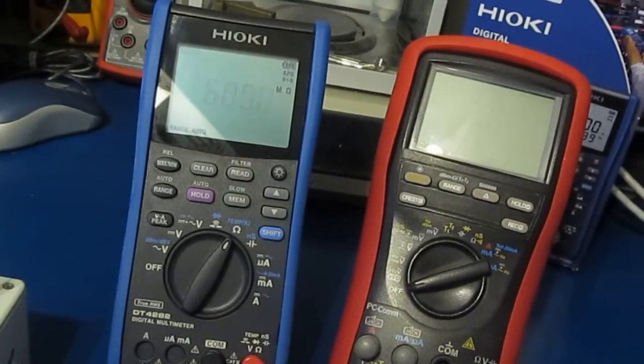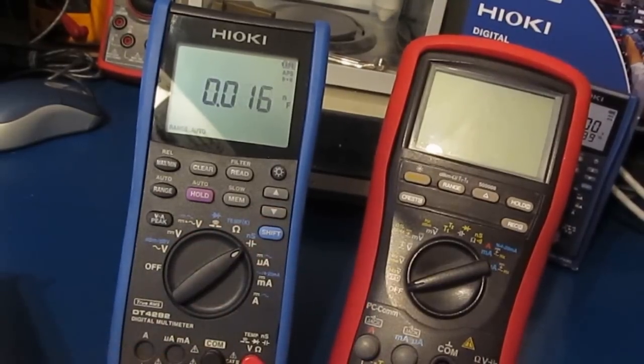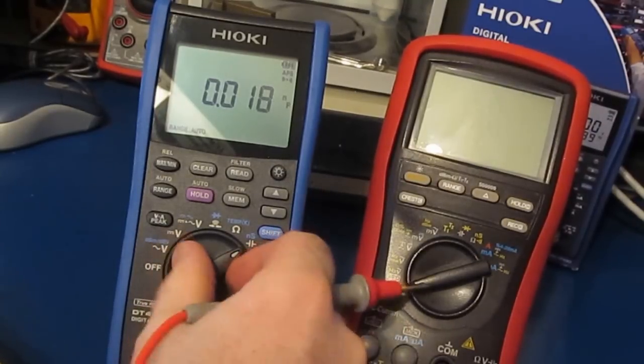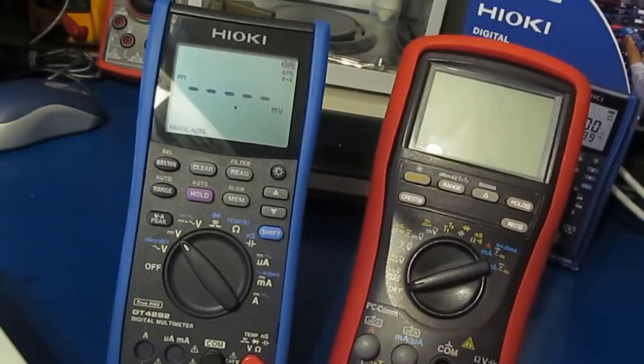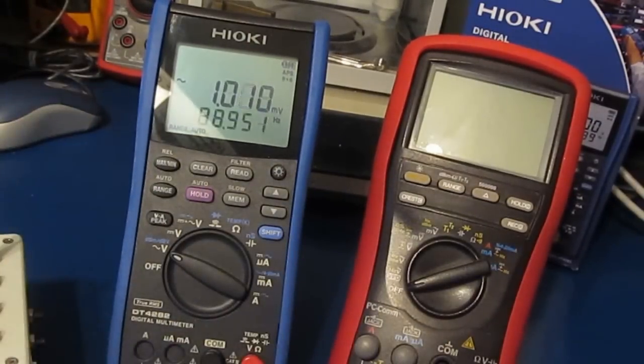Just do a real quick check again. This will be a dead short, 100, 1K, 10K, 100K, 1 meg, 10 meg, and let's just try it with capacitance real quick. So again, this will be 150 pF. Again, I have not zeroed this out. Here's a 0.1. Here's a 1 nanofarad. That looks all fine. Let's just check it in the DC volt mode real quick. Again, this should be 5 volts. Looks good. I'll go ahead and run an extensive functional test on it, but it looks like it survived that testing just fine. Alright, so our Hioki survived their gas grill test.